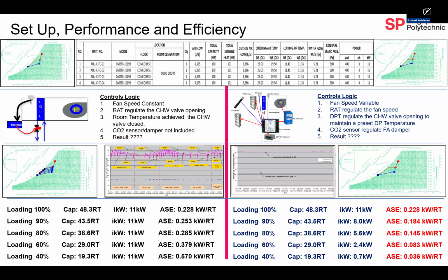If you set up the right side - since we put all our AHUs on VSDs, and now we have EC fans, even better - the relationship of power is still the same: as your load reduces, your power must reduce together. This is the importance of synchronizing your control, so that you maintain efficiency at all times, whether operating at 100% or at 40%. My efficiency will always be improved.